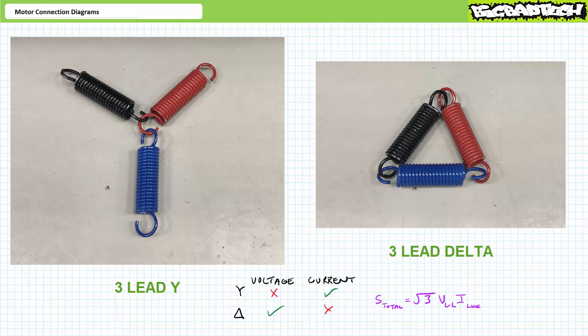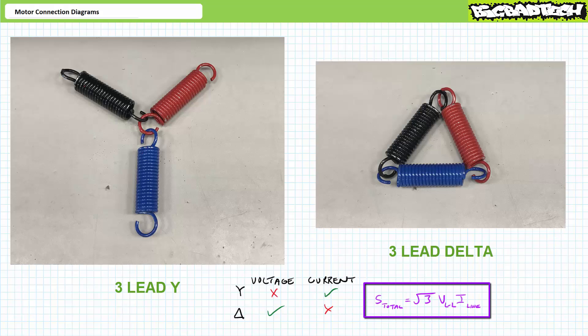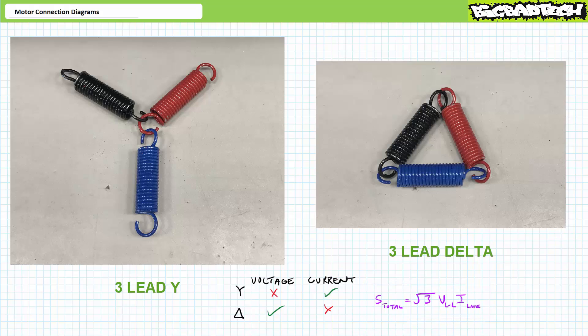For this reason, when working with balanced three-phase AC systems like three-phase AC motors, one customarily employs the single wattmeter method, which utilizes measurements entirely external to the motor. Line-to-line voltage measurement is external to the motor, as is the line current measurement. Total apparent power delivered to the motor is equal to square root three times the line-to-line voltage times the line current, regardless of the electrical configuration — Y or delta. Line-to-line voltage and line current readings are always an option because they're entirely external to the motor.